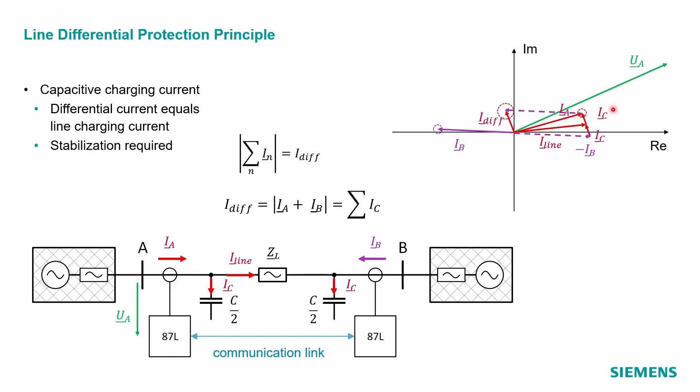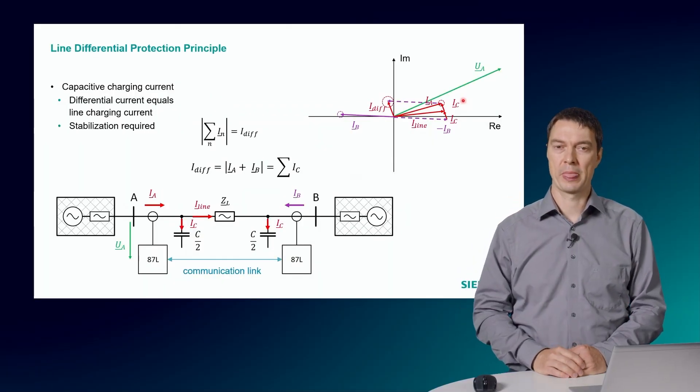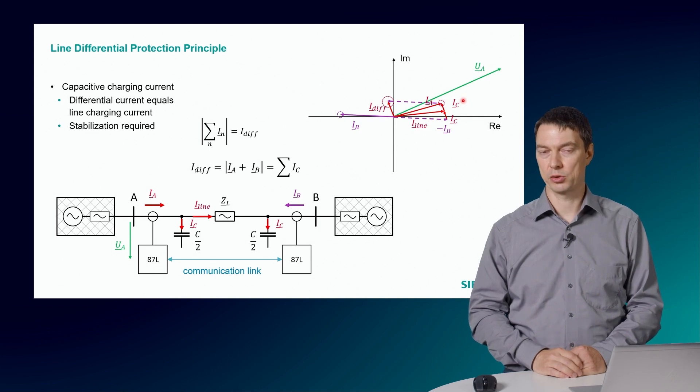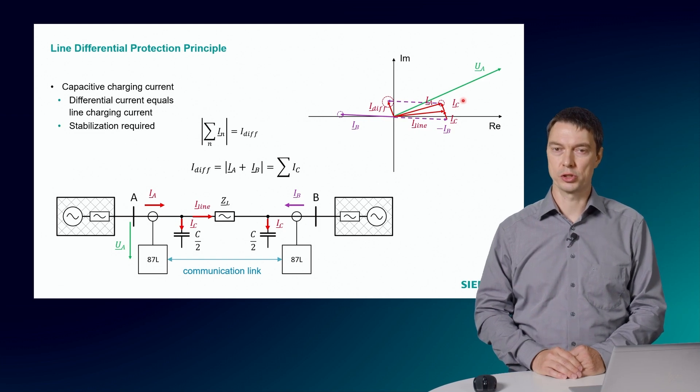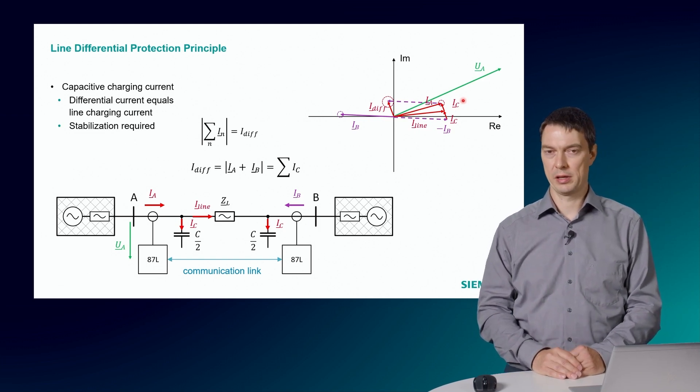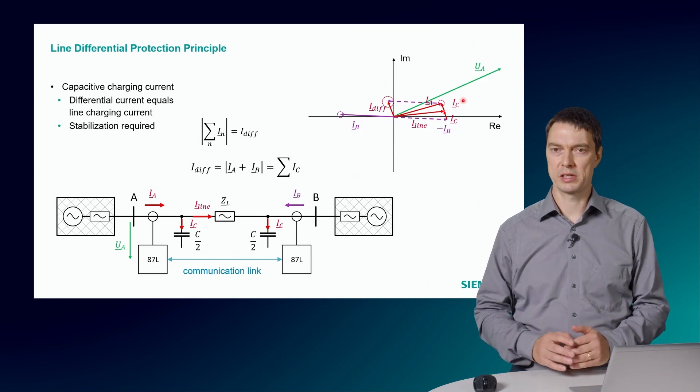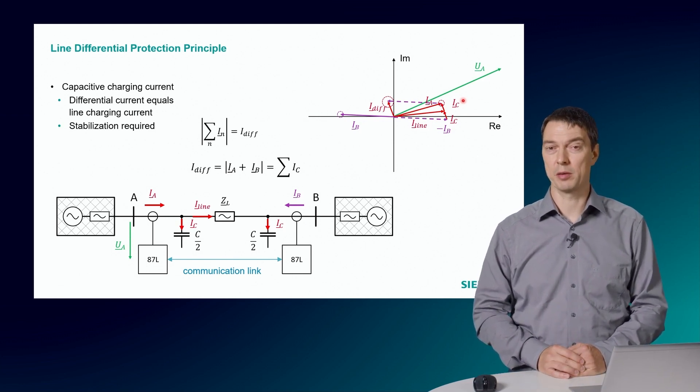This will result in quite a significant differential current, which is the charging current of the line. This needs to be considered for the relay setting. The minimum differential current pickup threshold must be set higher than this expected charging current. Many relays in the market also provide a capacitive charging current compensation. This requires a local measured voltage and will subtract the calculated charging current. The relay becomes more sensitive to low-fault currents but also requires a reliable voltage signal.